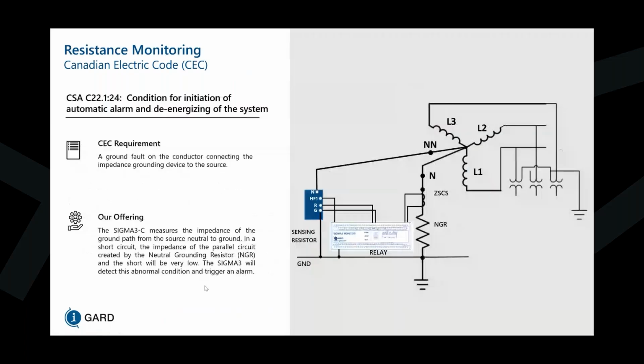Now, if we have a short circuit scenario and we're injecting this high frequency signal while there is 0 volts and 0 amps at the neutral, what happens is we get this full signal back because it bypasses the resistor and doesn't experience the voltage drop across the NGR. When the relay sees that the full signal has come back, then we can indicate a short circuit condition.